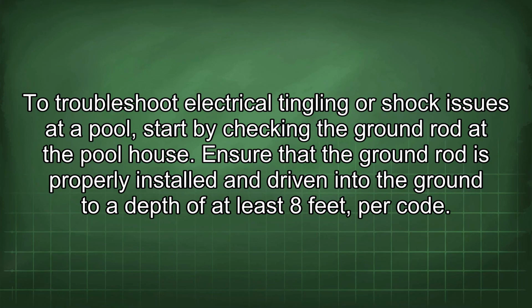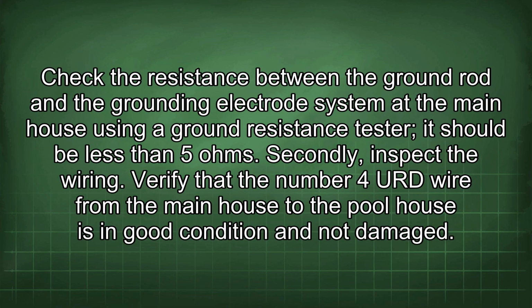To troubleshoot electrical tingling or shock issues at a pool, start by checking the ground rod at the pool house. Ensure that the ground rod is properly installed and driven into the ground to a depth of at least 8 feet per code. Check the resistance between the ground rod and the grounding electrode system at the main house using a ground resistance tester. It should be less than 5 ohms.